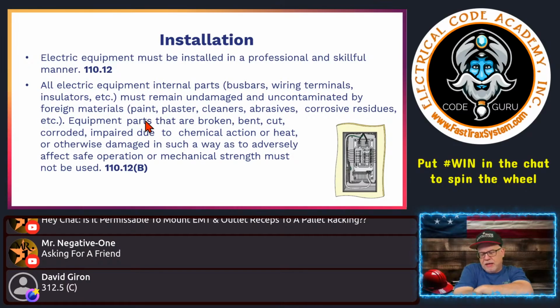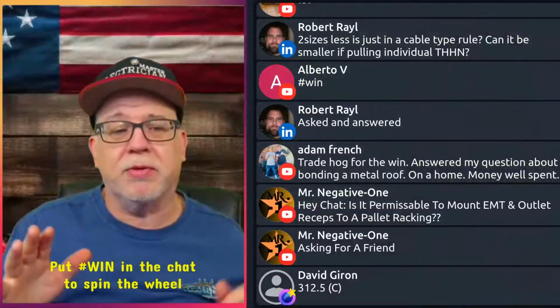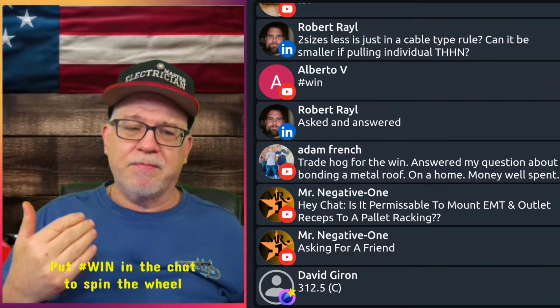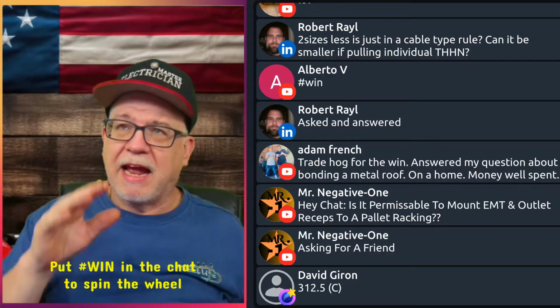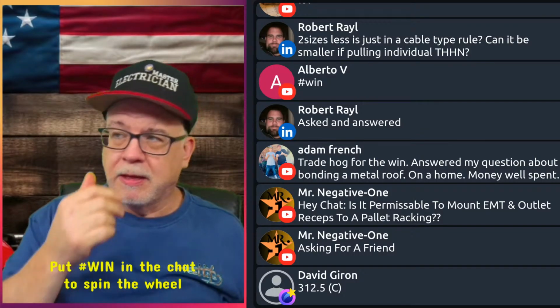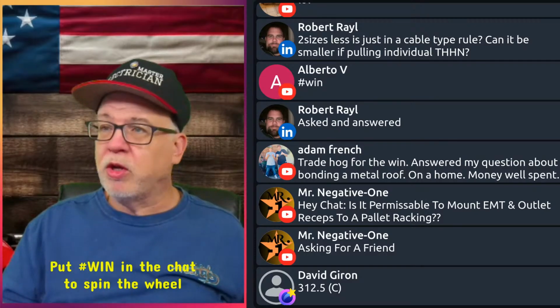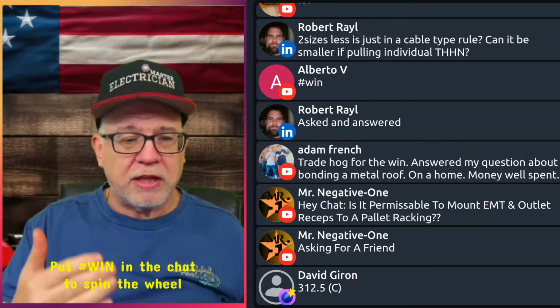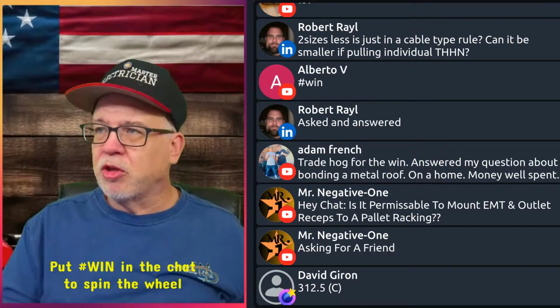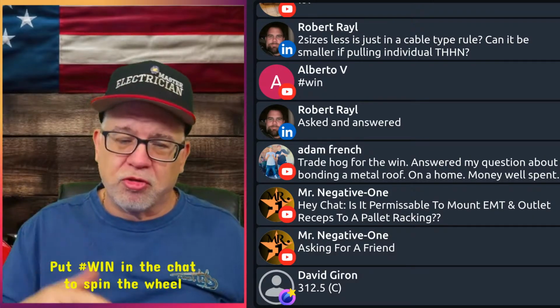I know he's being jokey, and I said paybacks are hell. But the reality is they're in there trying to get it done as quick as possible, and they could have some overspray, whether it's paint, plaster. You cannot, folks, just go in, and I know you say, oh, Paul, I'll do it anyway. Well, you do you, boo. But you cannot go into a panel and have a bus that's a conductive bus and turn around and use a cleaner on it. We don't know what adverse effects. It usually has a coating on it, protective coating. You're wiping that off. We don't know what's in the chemicals you're using.